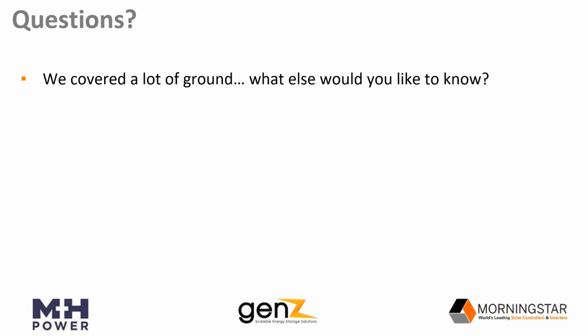If you want something a little more sophisticated, and I would say a safer solution, our ground fault protection device, the GFPD, can be added to either 150 volt or 600 volt systems. It's a product that Morningstar offers, and it uses a DC current differential, much more similar to how a ground fault protection device works on AC circuits, such as in wet locations in your home. It will meet the code requirements, and do a lot better job in terms of accuracy and detection. And it keeps the system grounded also during an event. So those are available. But to the original question, it is not integrated into the controllers; it is generally provided separately in the system.